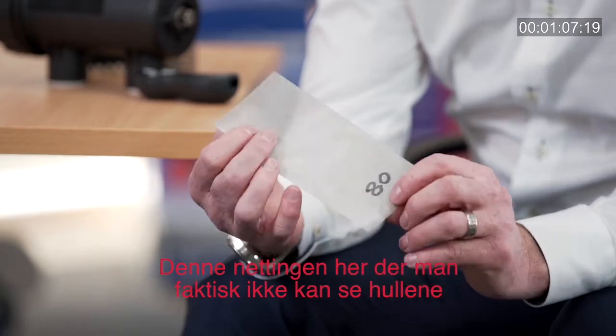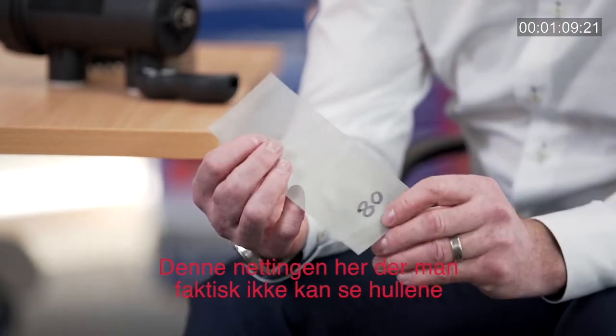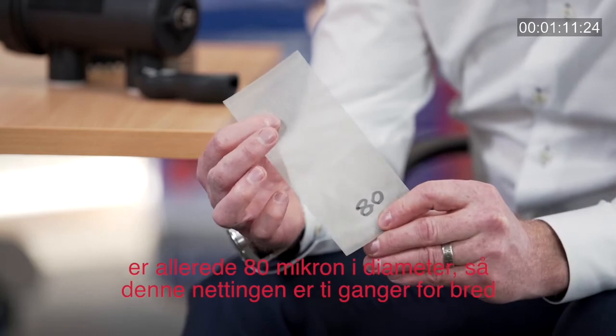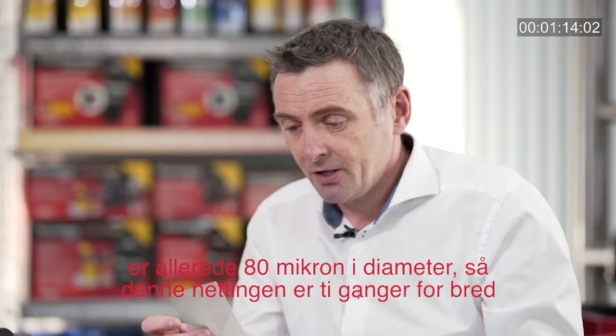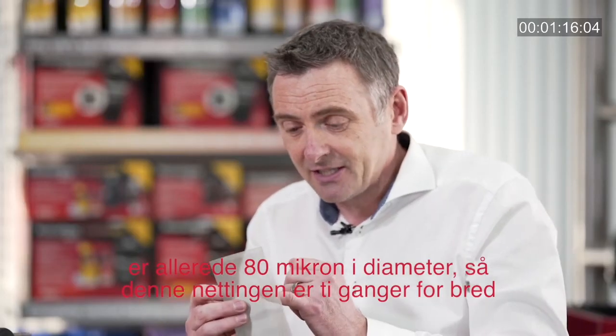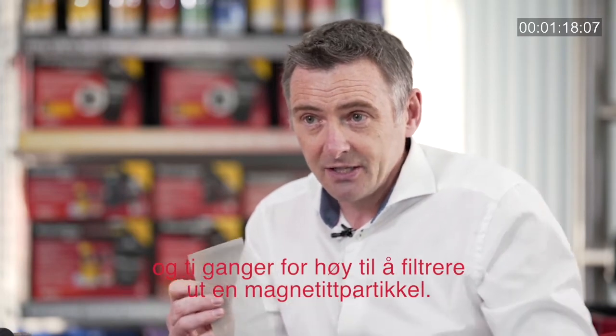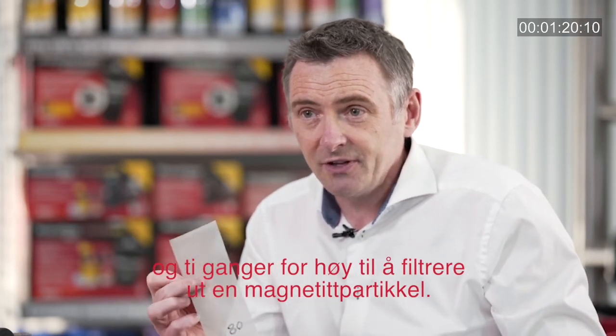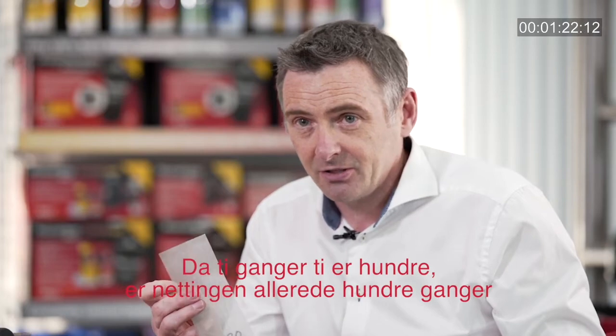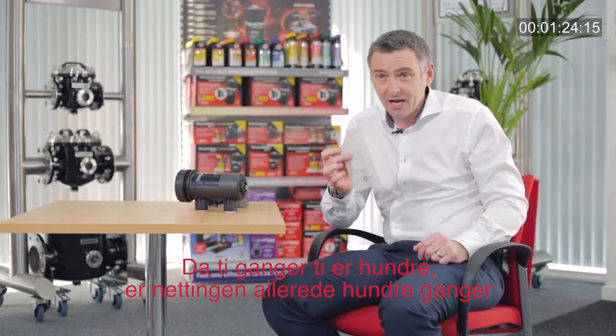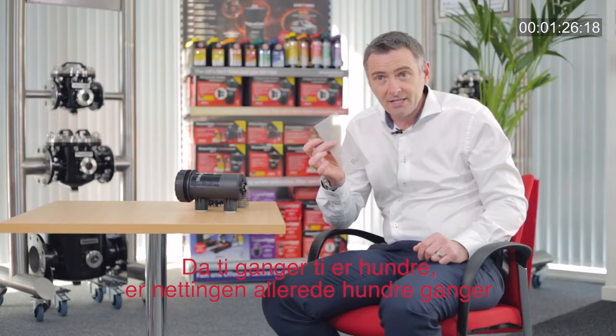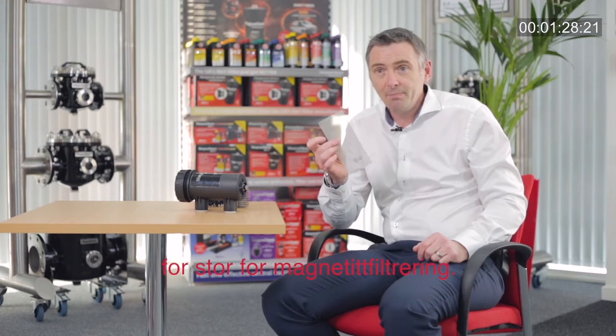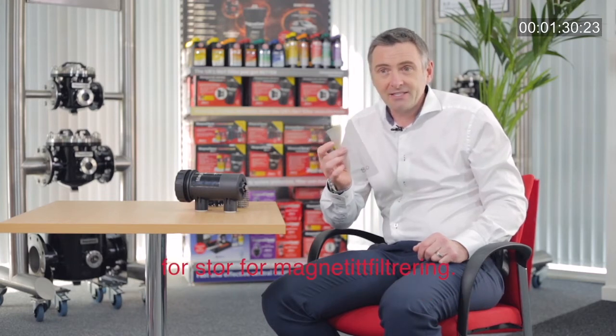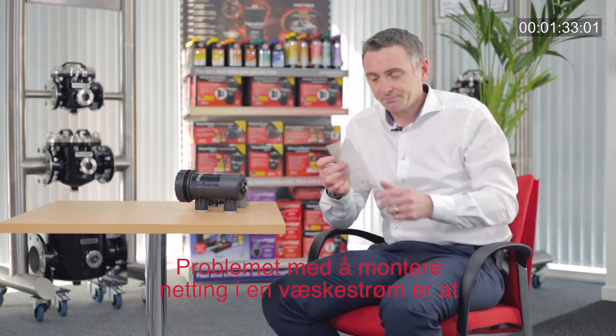Now, this mesh here, where you actually can't see the holes already, is 80 micron in diameter. So this mesh, in effect, is 10 times too wide and 10 times too tall to filter out a magnetite particle. So 10 by 10 is 100. This mesh is already 100 times too big for effective magnetite filtration.